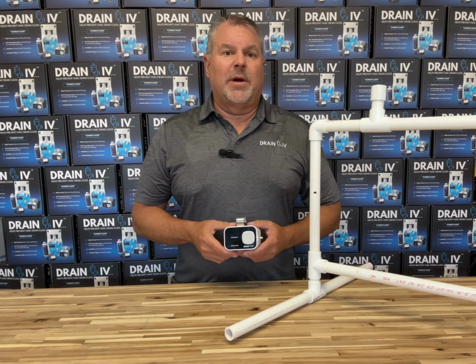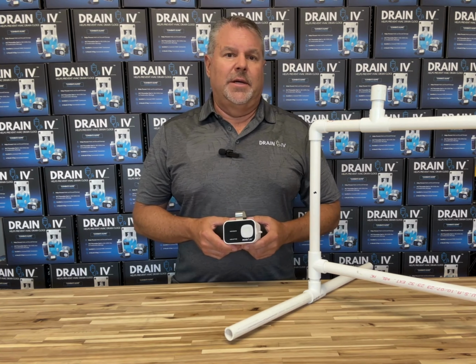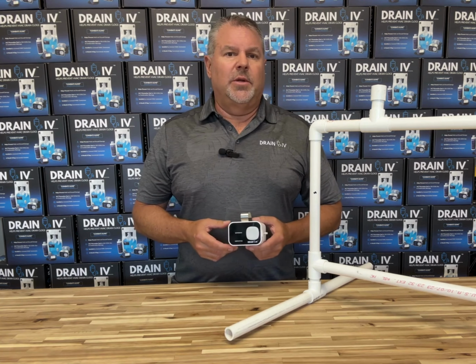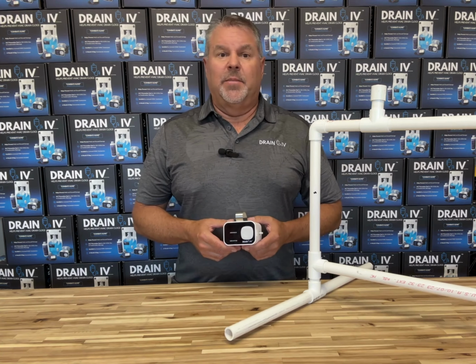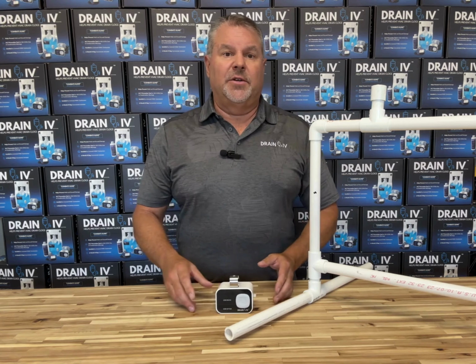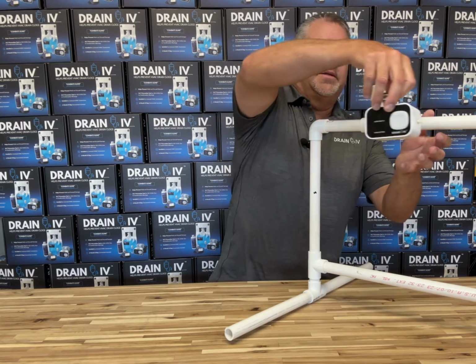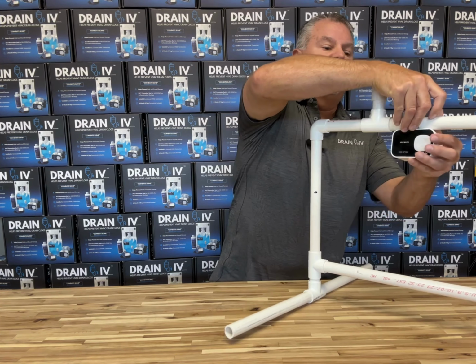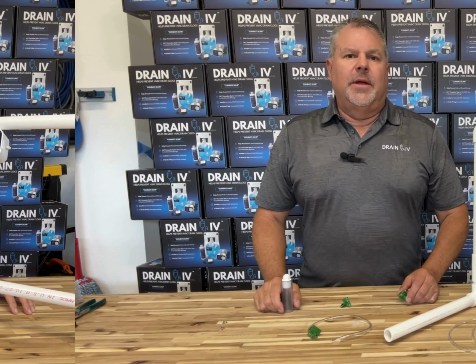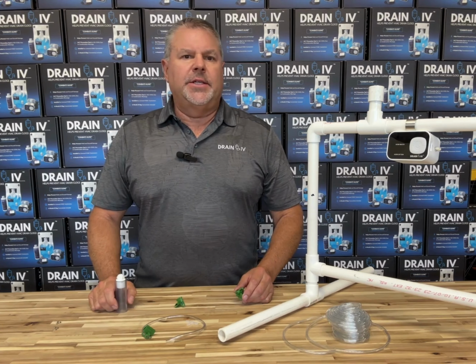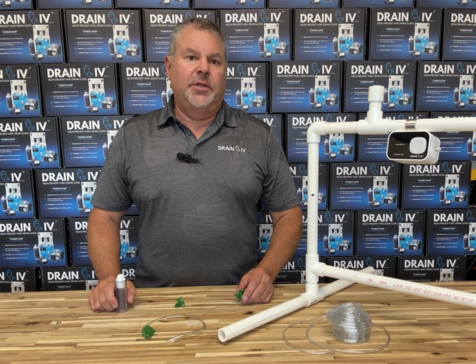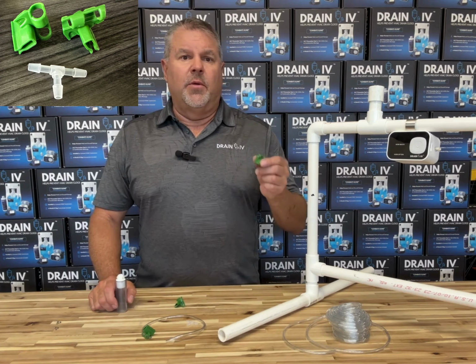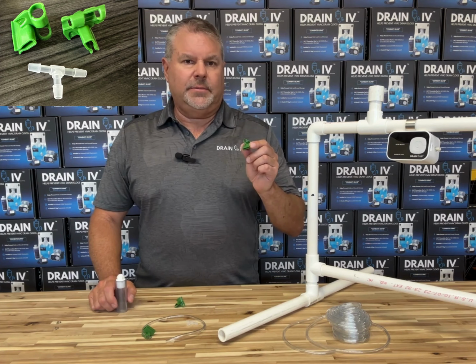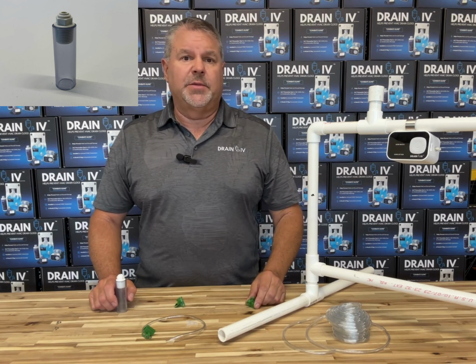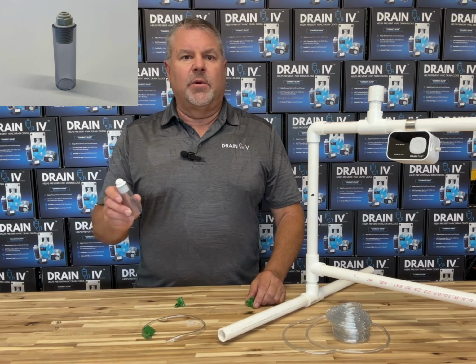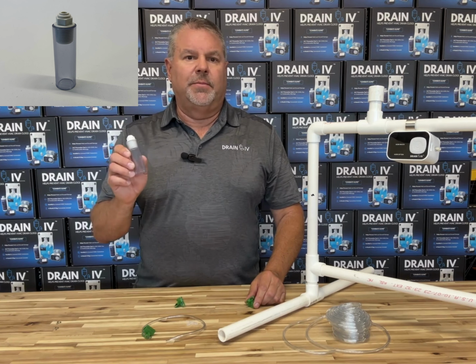Step 2, programmable pump and IV bag installation. First, you'll want to find a suitable location to mount the pump. The pump can simply sit on a flat surface, or the flexible mount can be formed around a pipe or something similar. There are 2 install options for injecting our agent into the drain system: directly into the condensate drip tray with our drip tray install kit, or into the 3/4-inch PVC access port just outside the air handler with our included clear injection port.